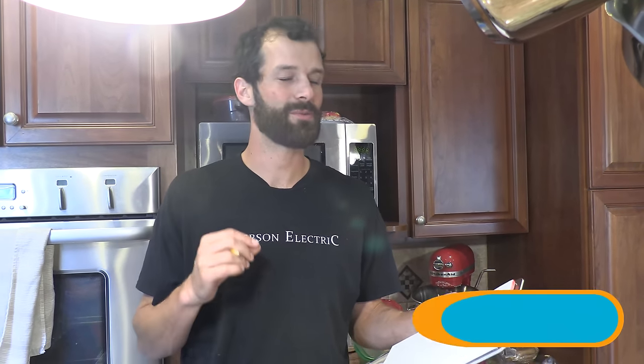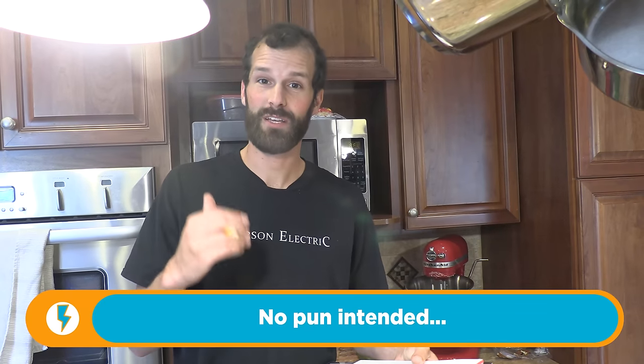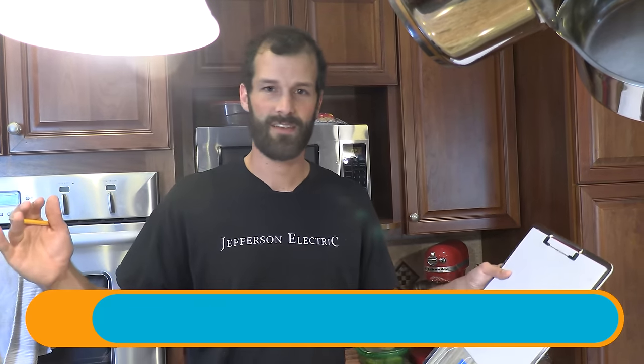One of the courtesy items, if you're an electrician after you've done this, is to offer to reset the clocks for the customer. You'd be surprised at how ticked people can be if you don't tell them on the front end. Now, you'll have to reset all your clocks and ensure all your appliances are working if you don't tell them on the front end, or at least offer to do that on the back end. And that's another 20, 30 minutes right there. Kind of hand-holding the customer through the home to make sure everything is just right. Because sometimes with an older electrical panel, what happens is you flip that breaker back on, and it goes to the on position, but truly this can happen. It doesn't actually re-engage the circuit. So now you've got a whole circuit that's off. So you want to verify the off, but you also want to verify the back on. Like I said, older panels, it's not a given.